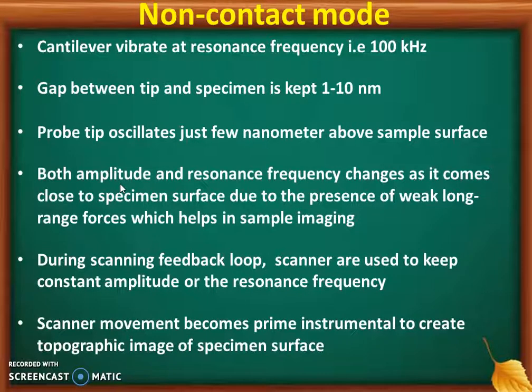If you look at the non-contact mode, here the cantilever vibrates at a resonance frequency of around 100 kHz. A very fine gap is maintained between tip and specimen, that is 1 to 10 nanometer. The probe tip oscillates just a few nanometers above the sample surface. So the tip doesn't touch the sample surface, but it doesn't have too much gap far away from the sample surface. Both amplitude and resonance frequency change as it comes close to the specimen surface due to the presence of weak long range forces, which helps in sample imaging.